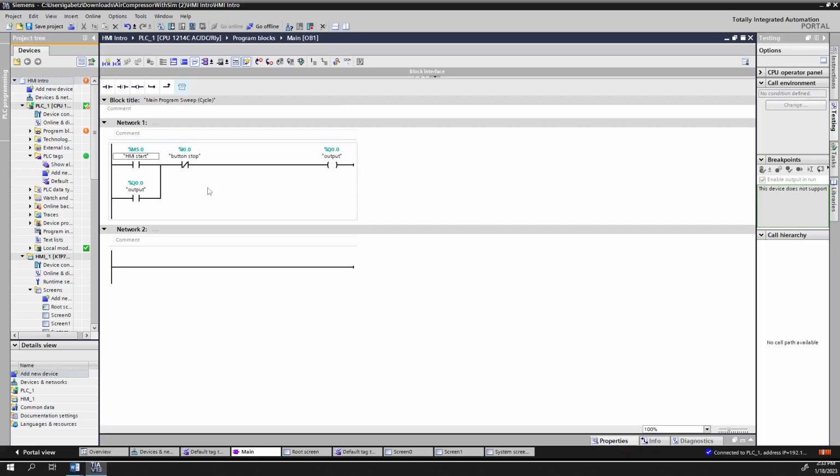All right, so you actually need to add the HMI start and the HMI stop in their correct locations. And just as a reminder for you, everything that is here in parallel with each other, those would be all start buttons. So these are all our start locations. And anything over here that would be in series in this blank space, those would all be stop conditions.